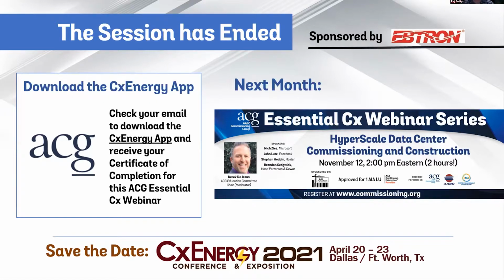What you need to also think about is there's 8760 hours in a year. Think about what you can do with the unoccupied hours during this pandemic mode. Think about altering your temperature resets. We are changing some of our supply temperatures and return air. Looking at that, maybe instead of going from fresh air at neutral and unoccupied, you might bump it up or bump it down based on the season. Focus on energy savings during unoccupied.